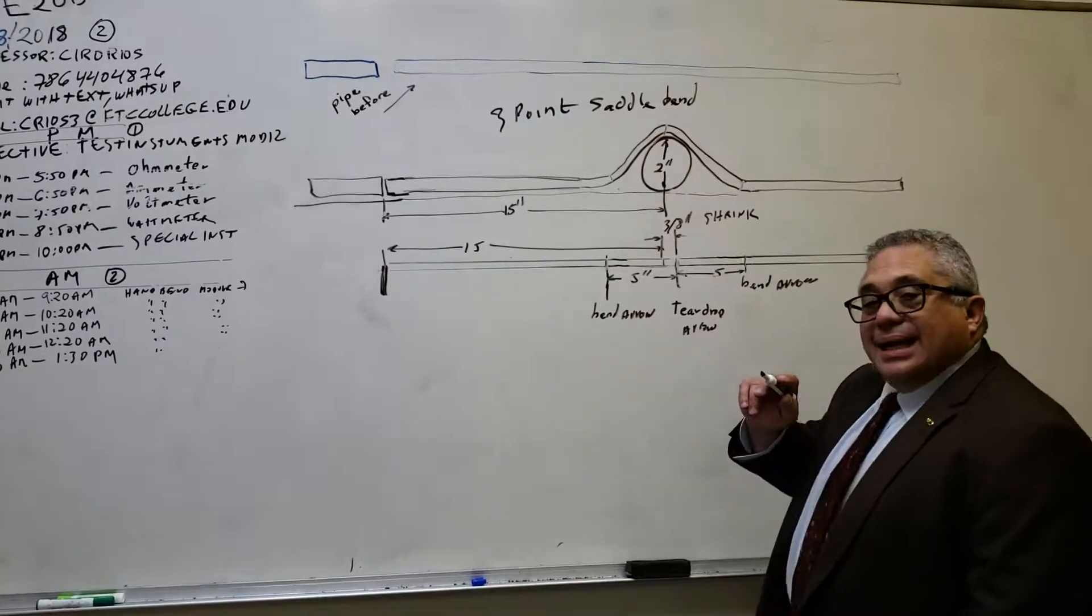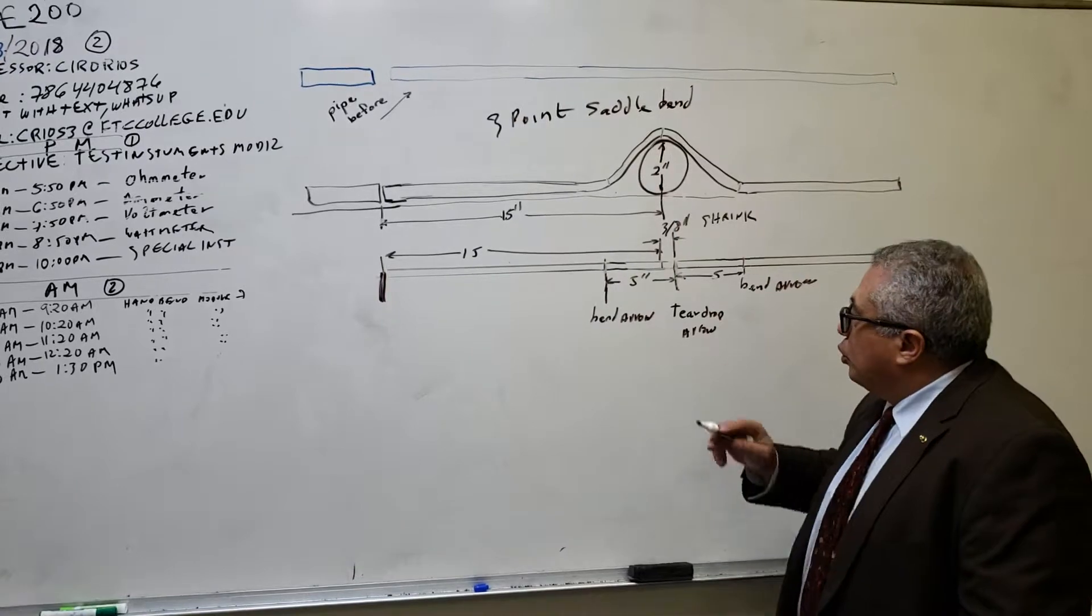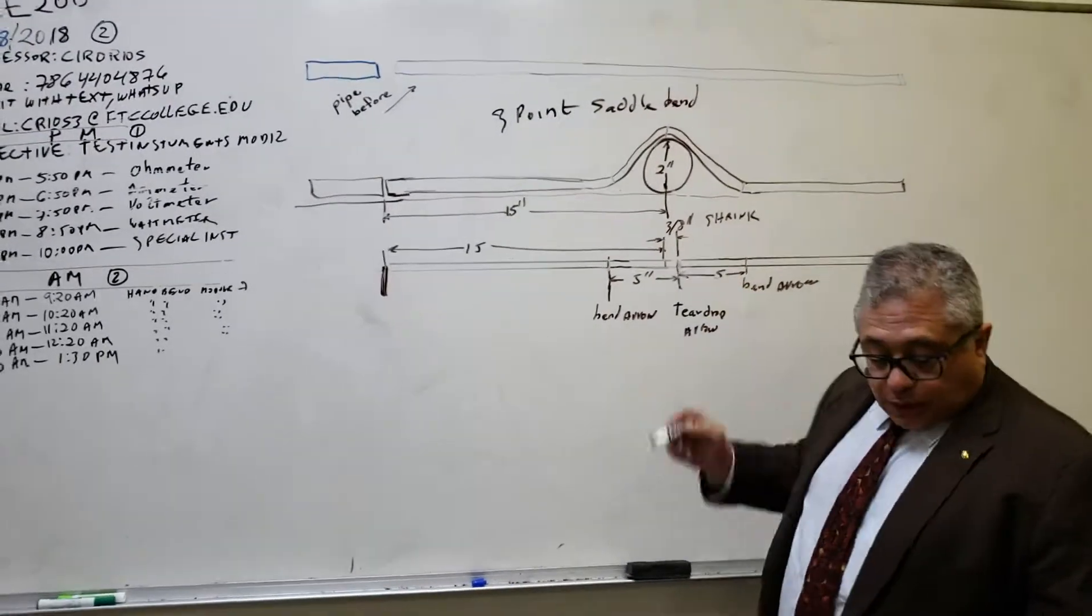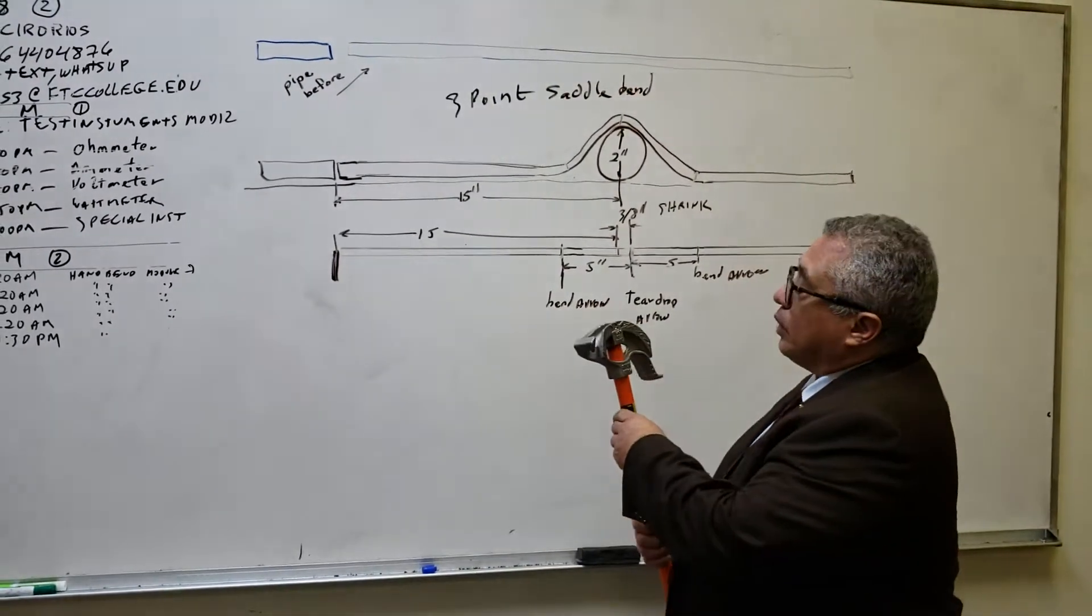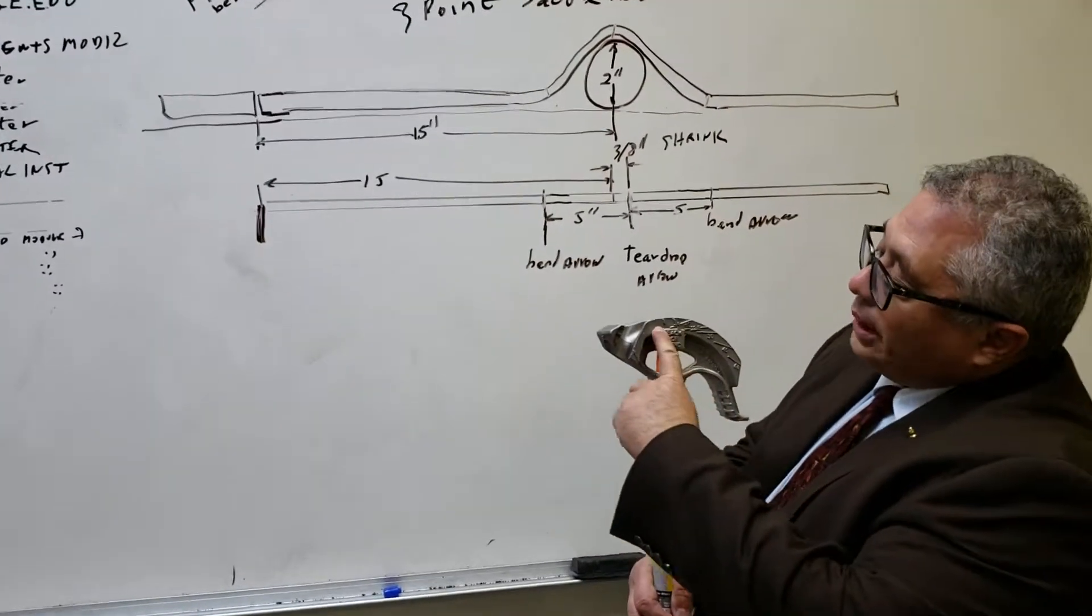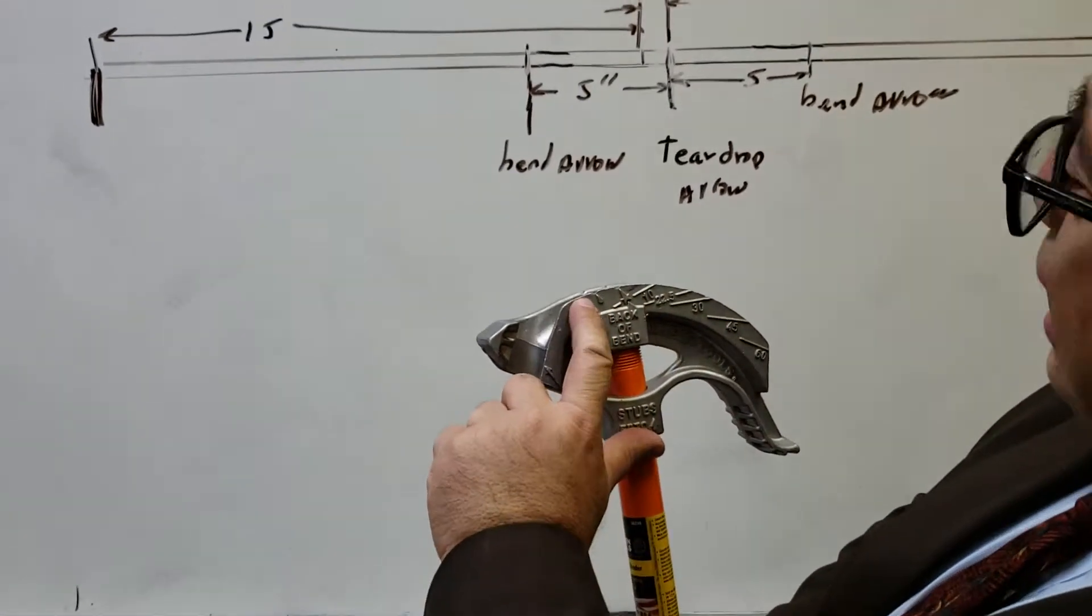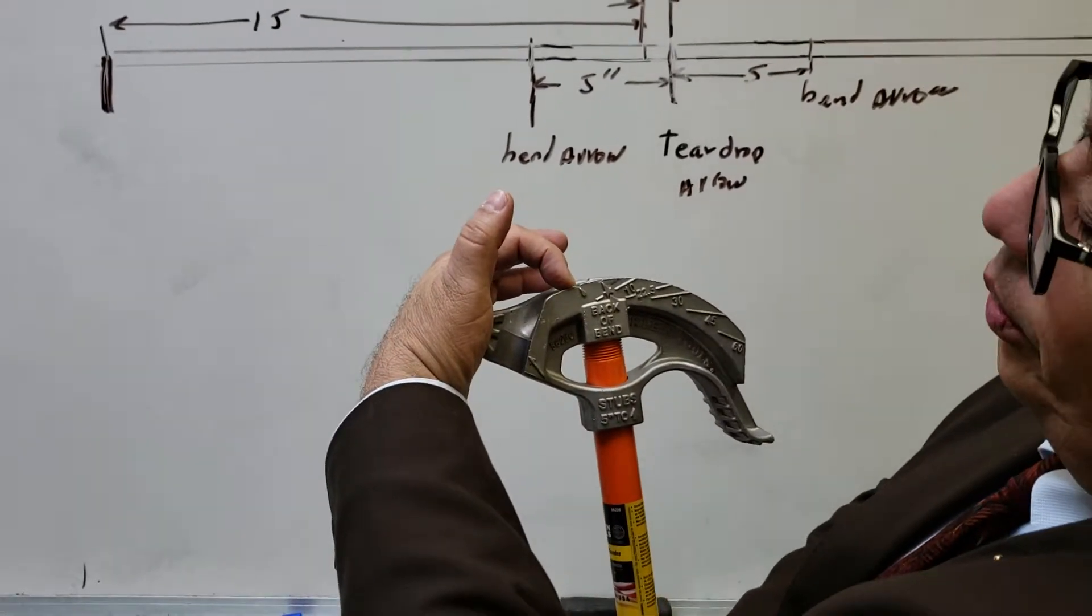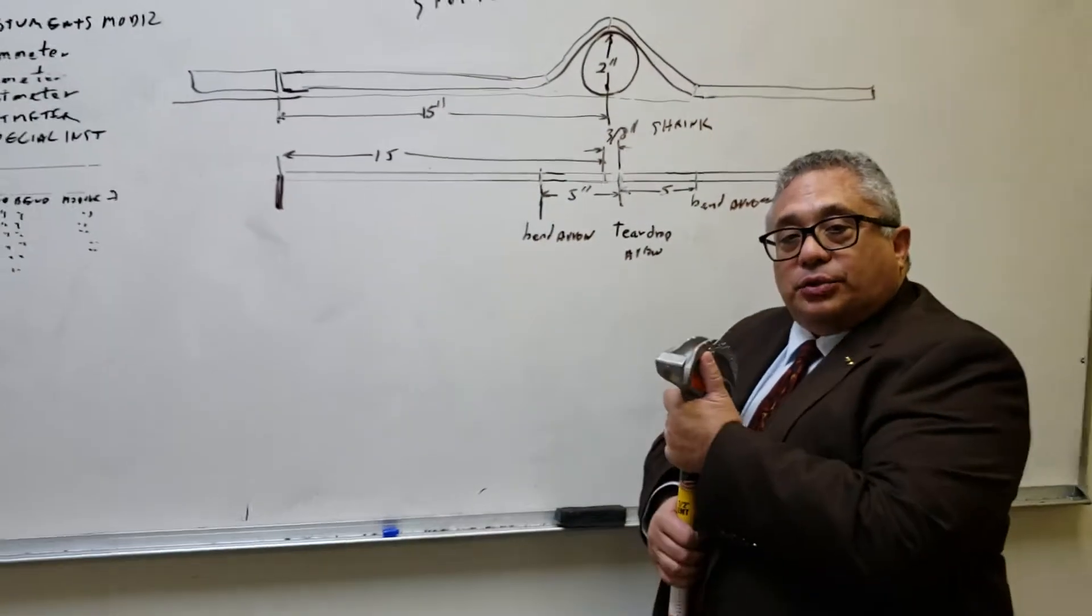One more detail. In order to bend this pipe, this conduit, the first thing you need to do is to bend the center mark. At the center mark, you bend 45 degrees with the back of bent arrow. No, it's not the back of bent arrow, it's called a tear drop arrow. This one that is over here. Tear drop arrow. That happens to be the center of that 45 degree bend.